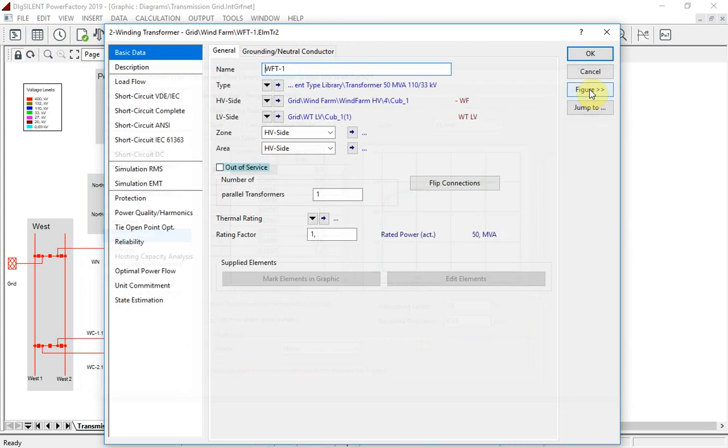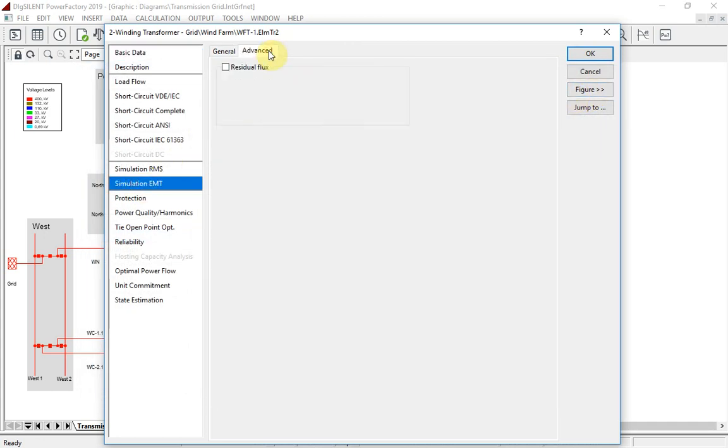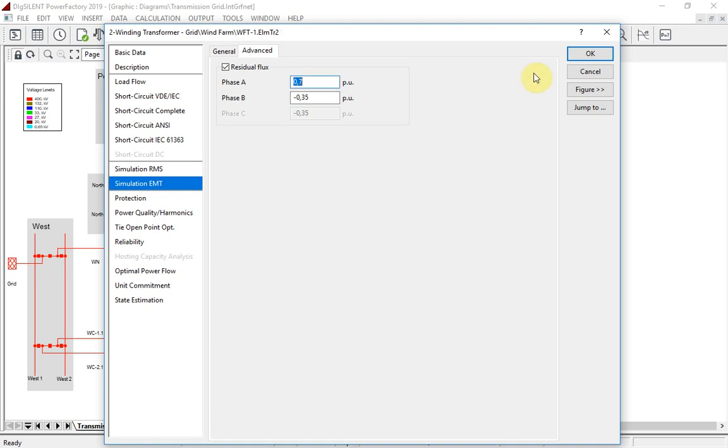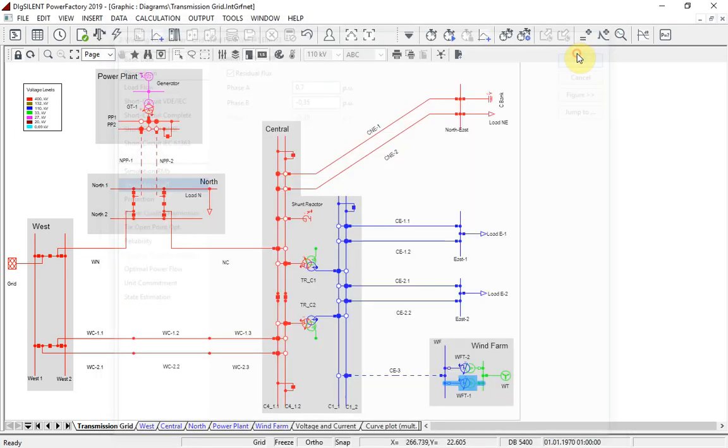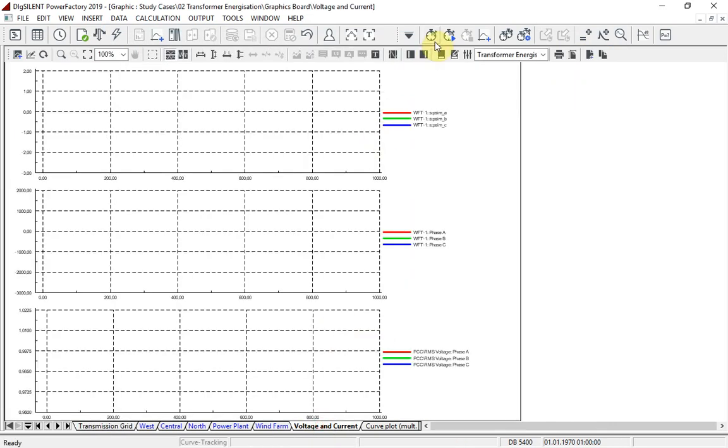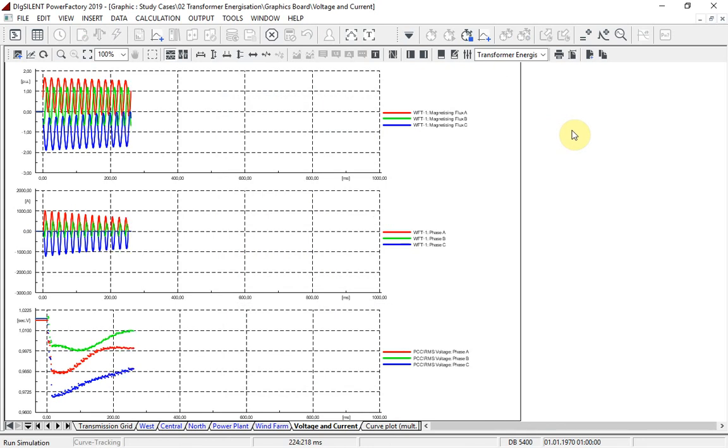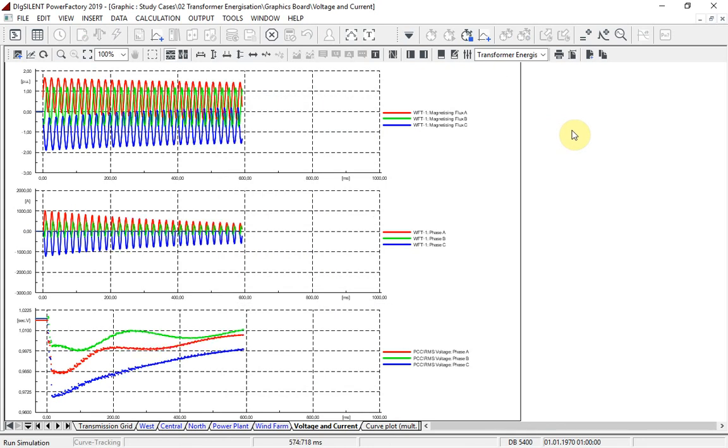In version 2019, the user can also define the residual flux of the transformer in the element, directly for each phase. This represents the remaining flux in the transformer after disconnection. We will now show the effect of the transformer saturation during energization.